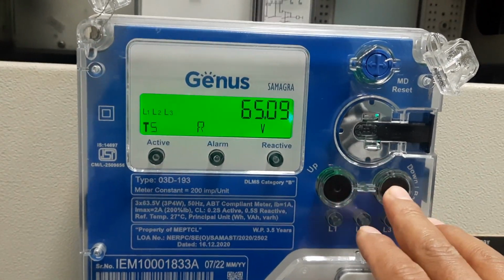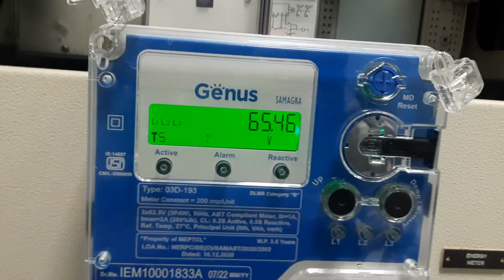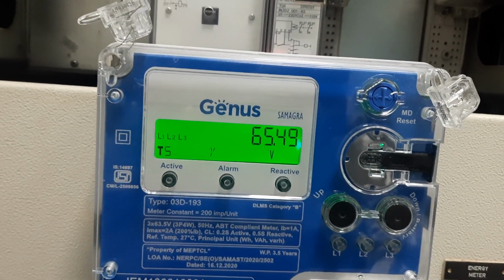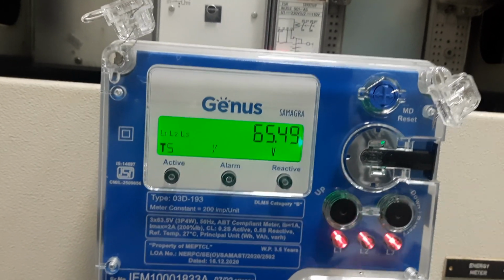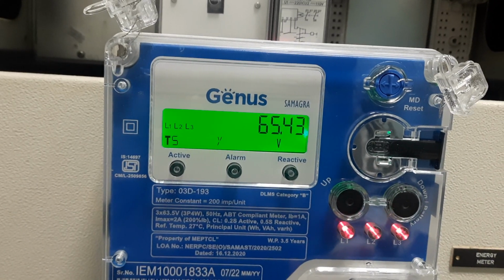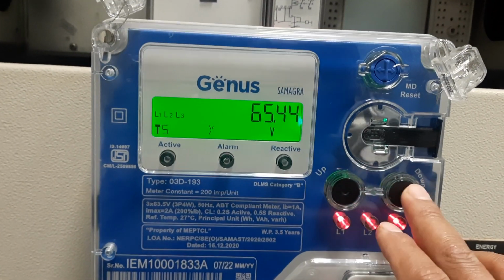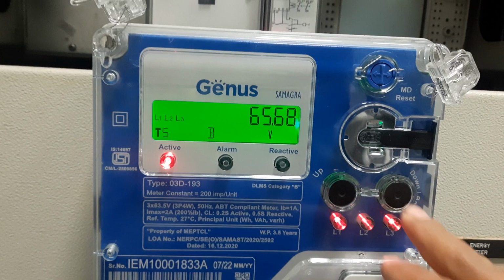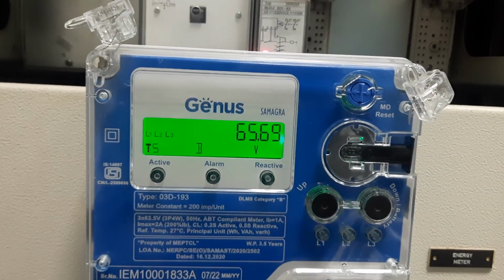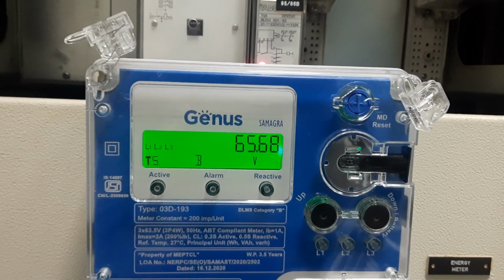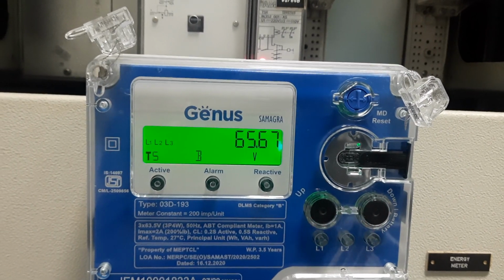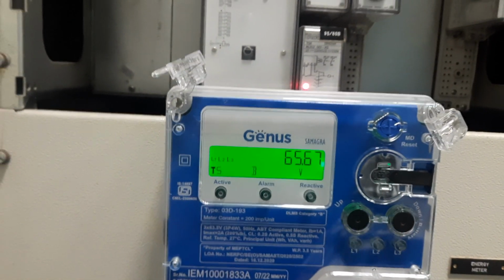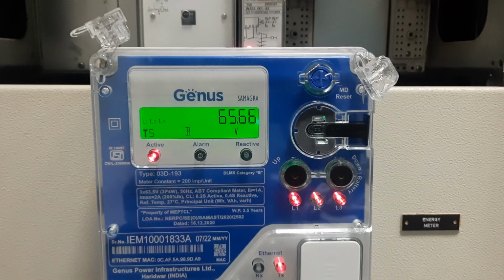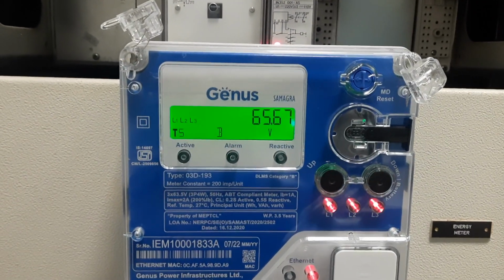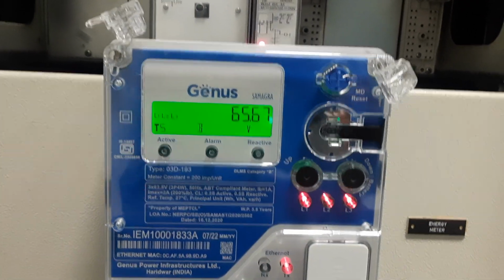Then let us take Y phase. Our Y phase is 65.47, because our primary voltage is a little on the higher side. Then B phase to earth is 65.65. I'm getting this value because the primary is a little on the higher side. It's not 132, maybe 134. Accordingly, our secondary values will be this much. So this is how you verify the voltage. Voltage is now done.